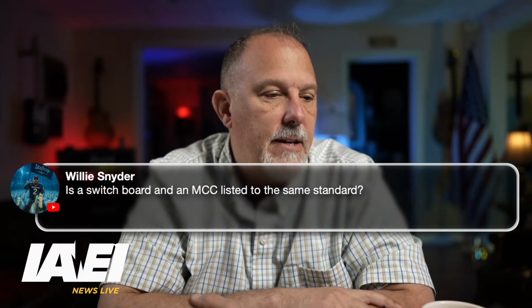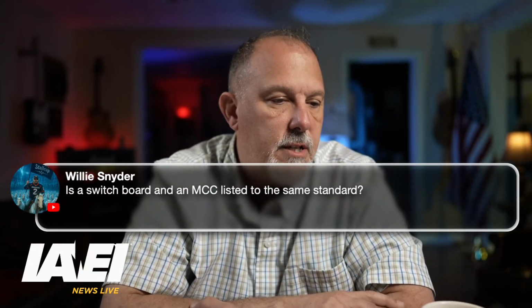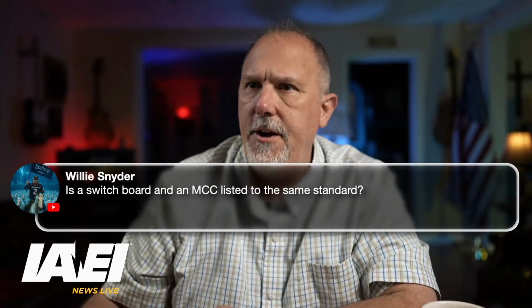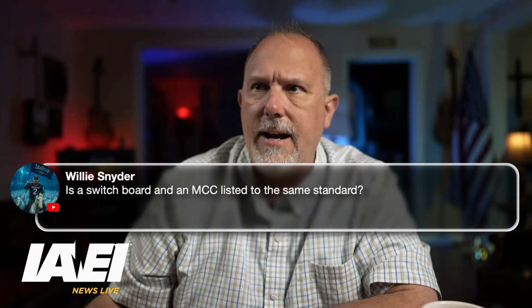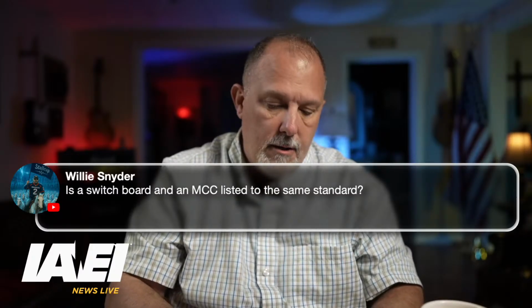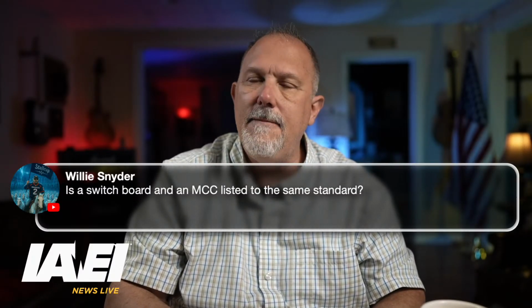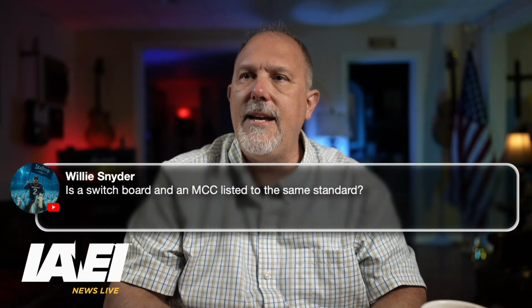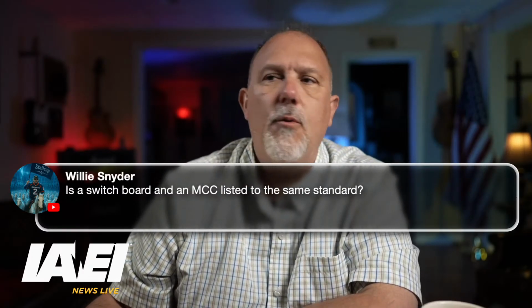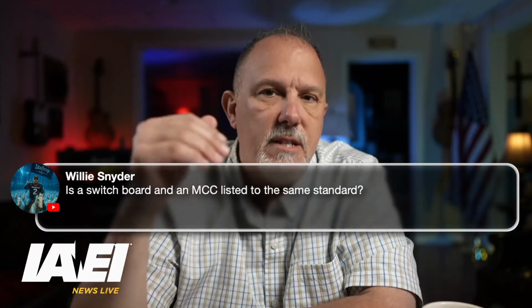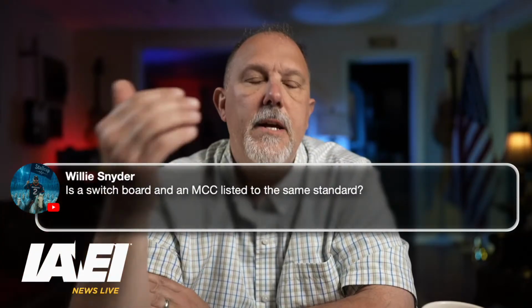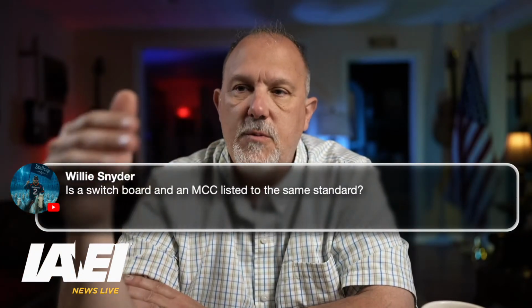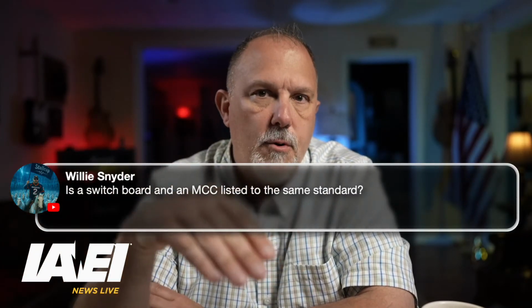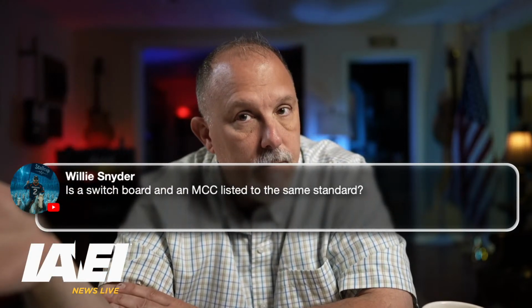Mr. Snyder, is a switchboard and a motor control center listed to the same standard? No. Switchboards are UL 891, but they're similar. MCC, I can't remember what an MCC is listed to—845. Motor control centers are listed to UL 845. Switchboards are 891. Panel boards are UL 67.